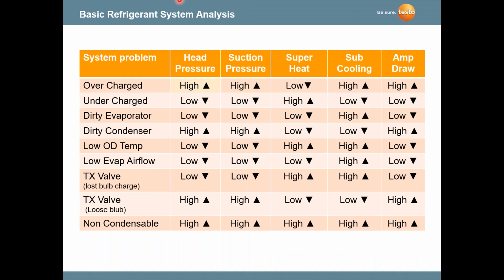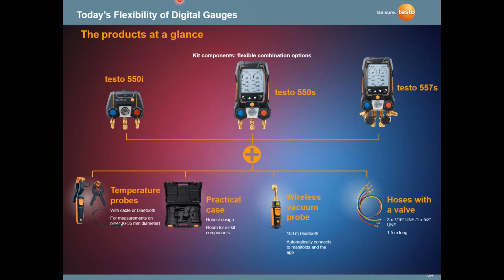There's other things you could do with digital gauges, of course. You can diagnose system problems. Just a chart here looking at high pressure, low pressure, superheat, subcooling, looking at what's happening. You can determine the symptom or the problem that is occurring in the system by looking at a combination of the measurements that are coming off of the gauges. A lot of different ways, a lot of different flexibility in these gauges today.